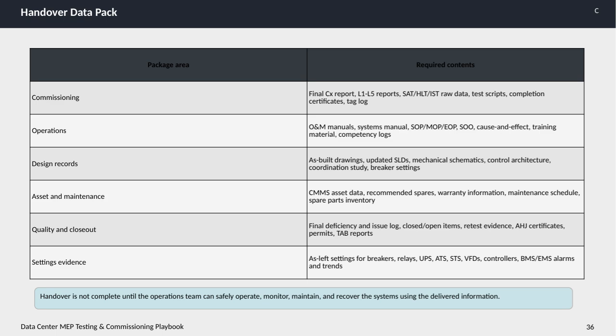Quality and closeout documentation must cover the final deficiency and issue logs, status of open and closed items, retest evidence, certificates from authorities having jurisdiction, permits and testing, adjusting, and balancing reports. These documents confirm that all quality requirements have been met and the project is properly closed out. Lastly, settings evidence contains as-left settings for everything from breakers, relays, UPS, ATS, and STS, to variable frequency drives, controllers, and building or energy management systems, alarms, and trends. This information is critical for ongoing system stability and troubleshooting.